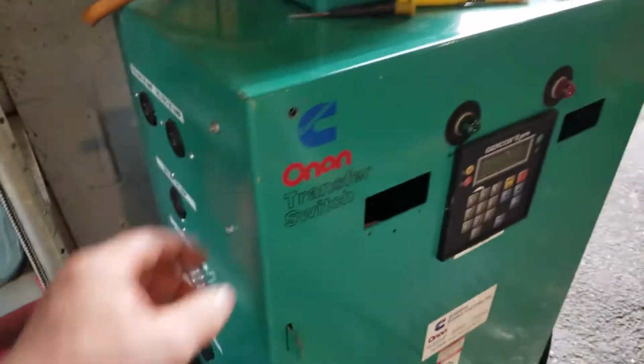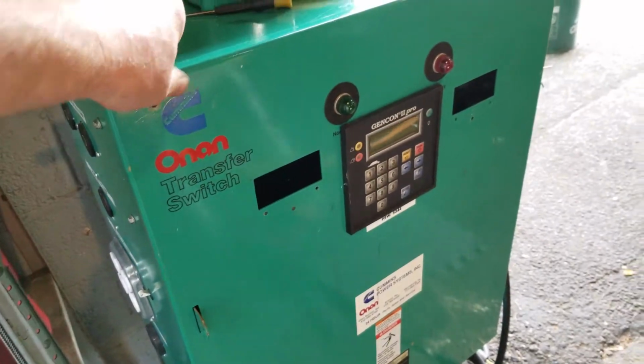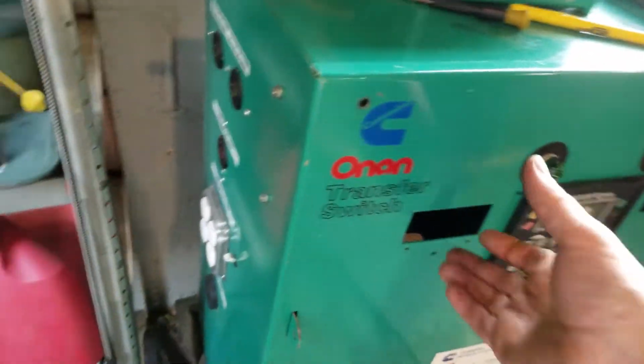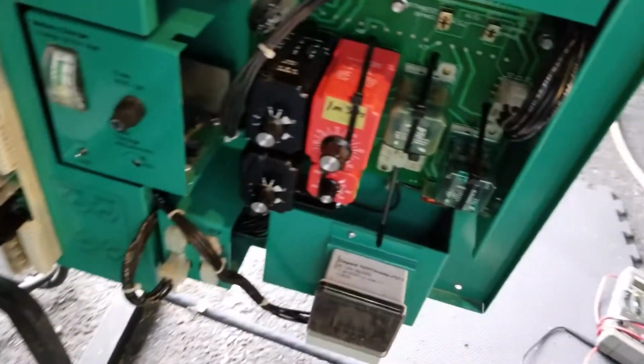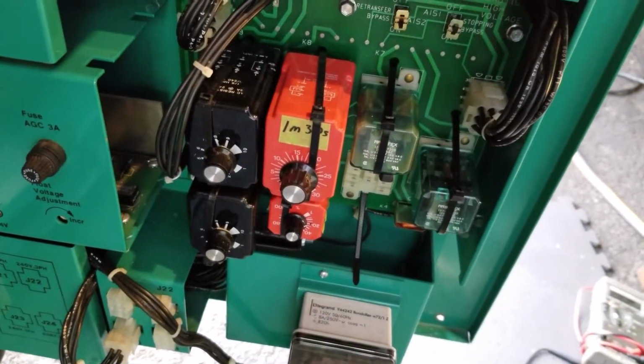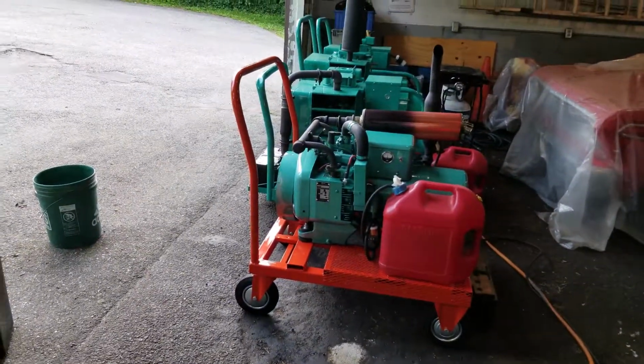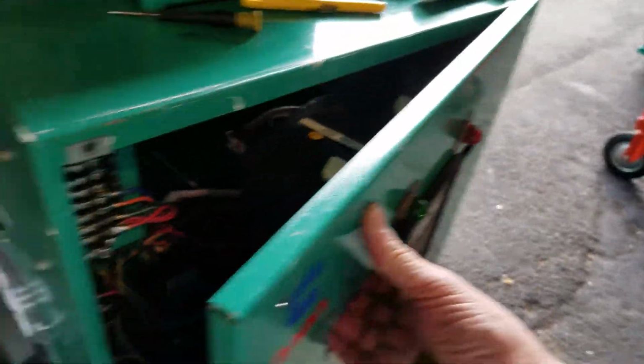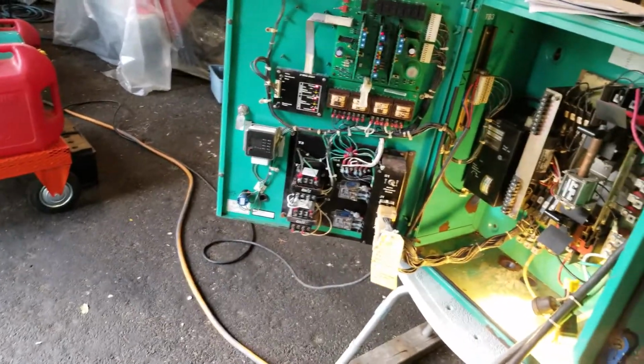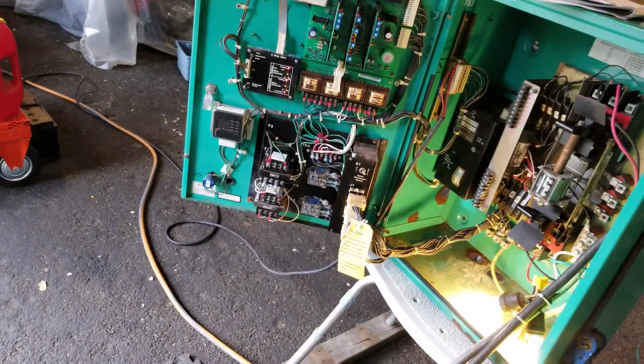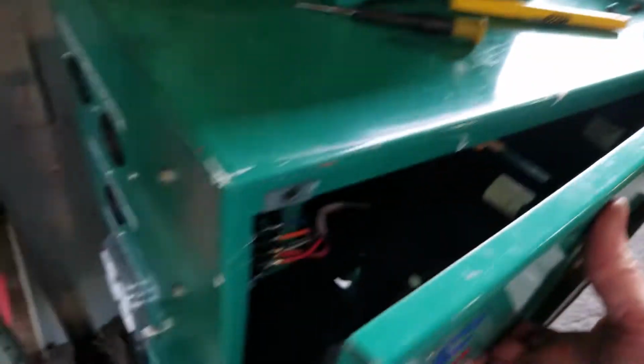I do have another transfer switch here. It's an older one, less complicated. It basically runs by relays, and if I want to change anything, these relays are quite expensive. This does work, and I did have it hooked up to the same generator over there, but I disconnected this automatic transfer switch because we're trying to troubleshoot that one. If I could get that one going, I'd rather use that one, but there's absolutely nothing wrong with this one right here.